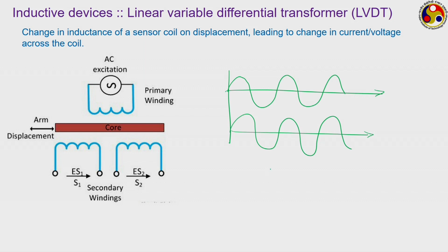Under normal situation, ES1 equals ES2 when the core is in its normal, or null, position, so ES1 minus ES2 equals 0. However, when the core is moved because of some displacement, ES1 minus ES2 will not be equal to 0, giving an output voltage directly proportional to the displacement of the core. That is the operating principle of LVDT, or generally any kind of inductive device.